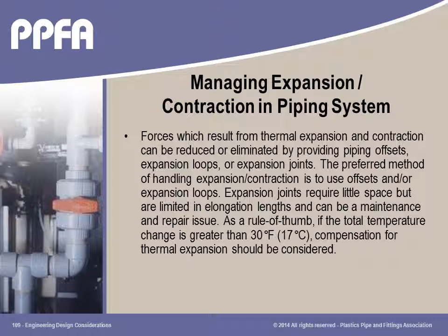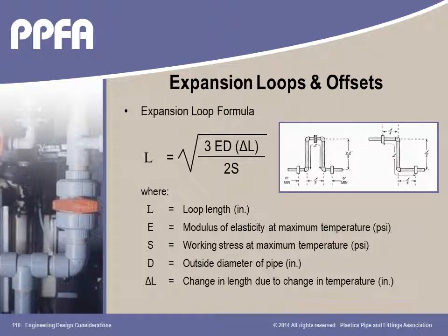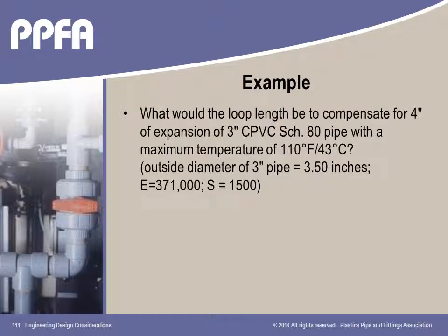Managing the expansion and contraction of thermoplastic piping systems is similar to other piping systems. Like other piping systems, expansion loops are the preferred methods of handling this phenomenon. Fabricated or bellows type expansion joints can be installed, but should be used as a last resort because of increased maintenance, lower reliability, and usually increased cost. Using the expansion loop formula, the loop length may be calculated based on the conditions of service, piping material, and piping diameter as shown in this example.